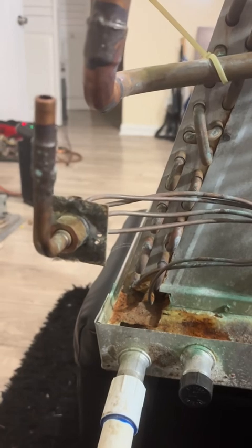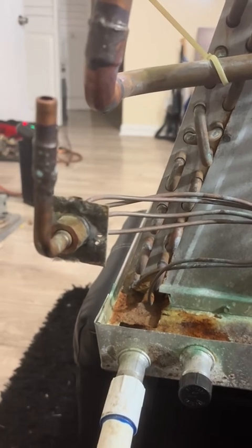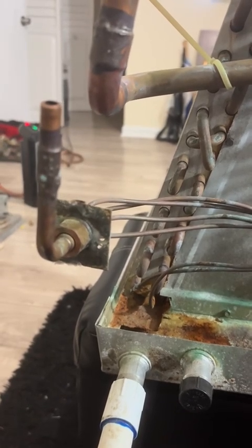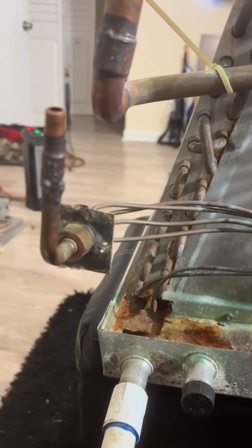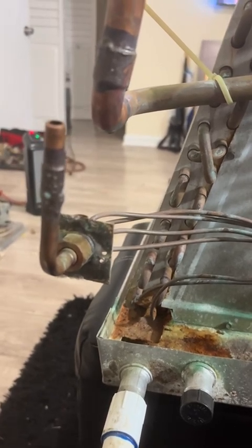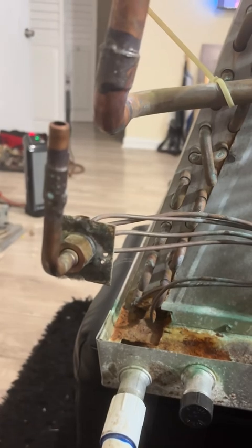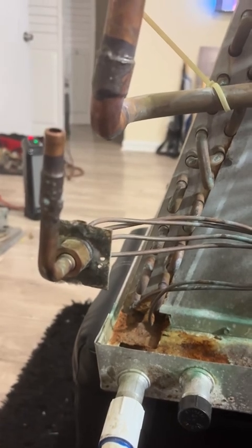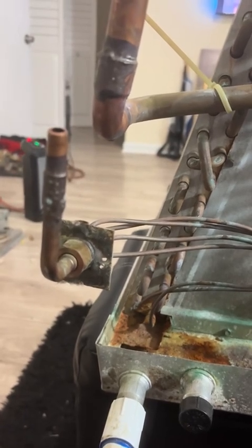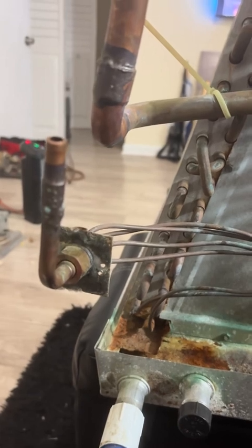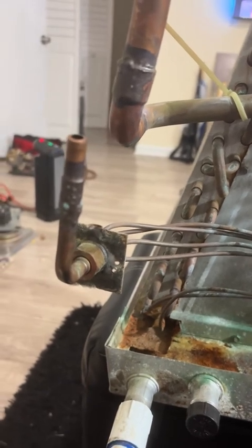It is essentially a piece of brass with a hole in the center. The smaller the bore, the less refrigerant flows through the piston, and vice versa. The advantages of a piston is that it is simple and can still be removed. You can also change the bore size and clean it if need be.